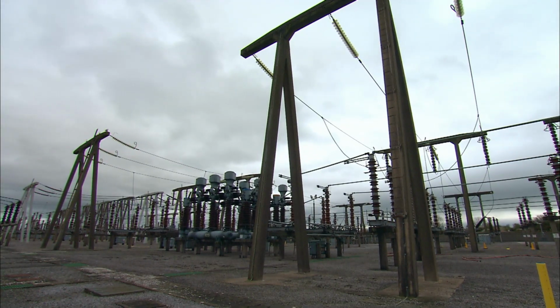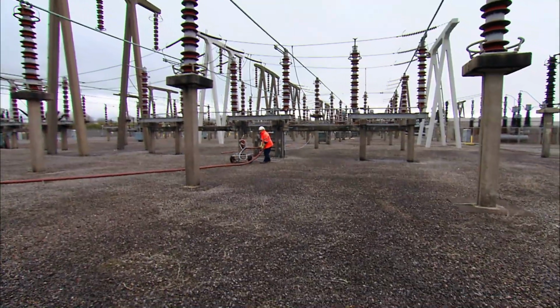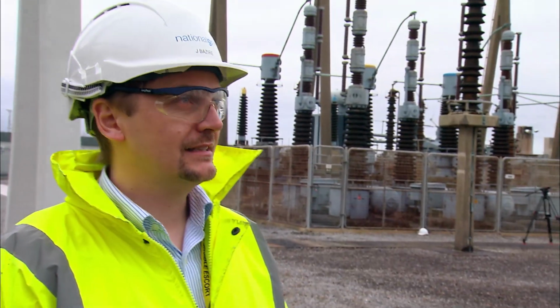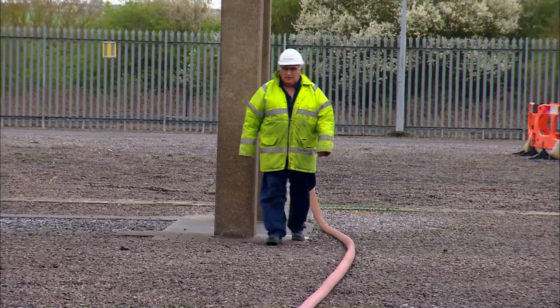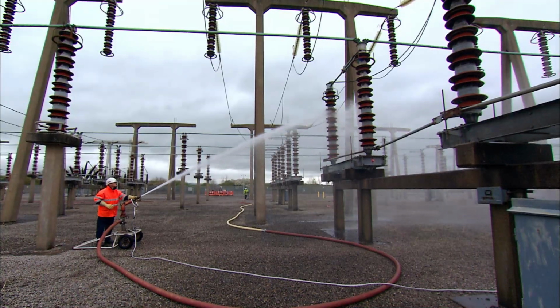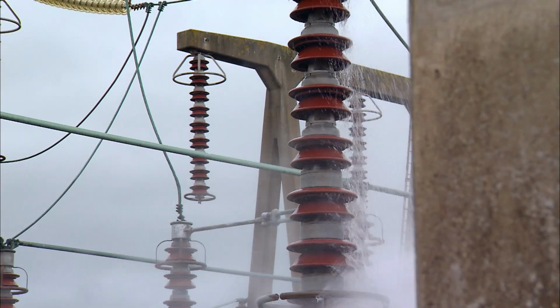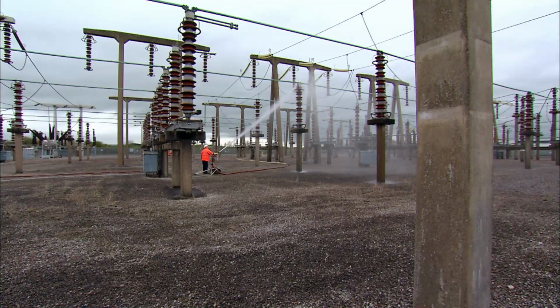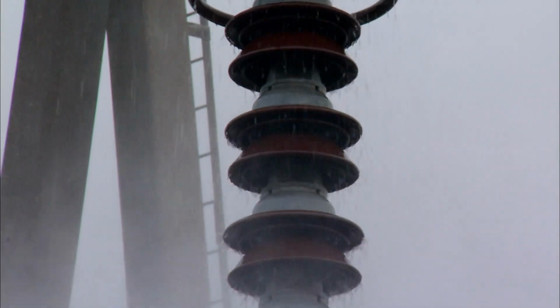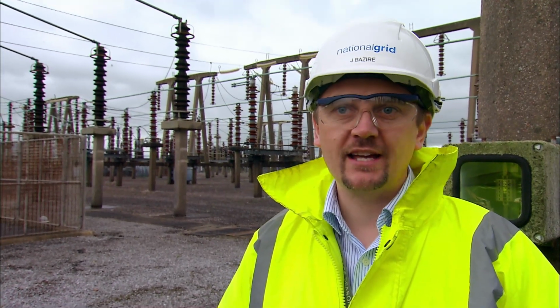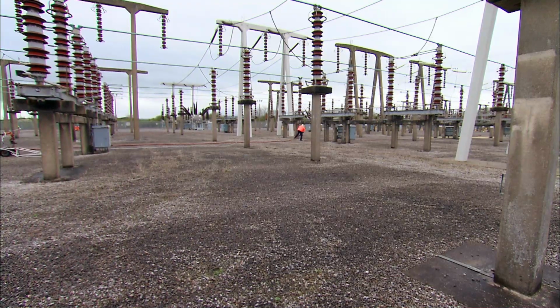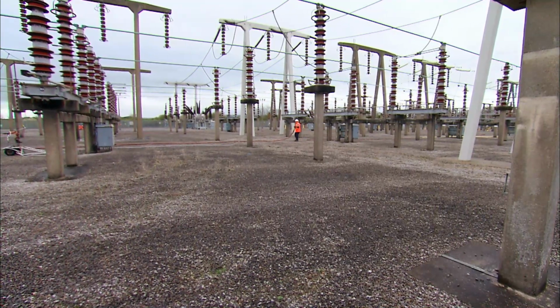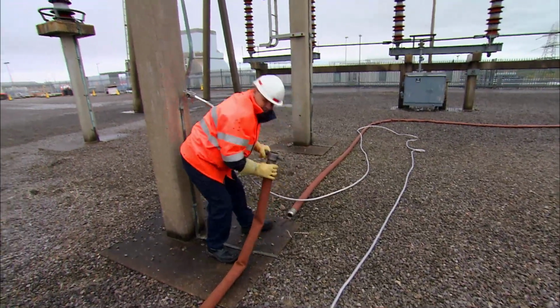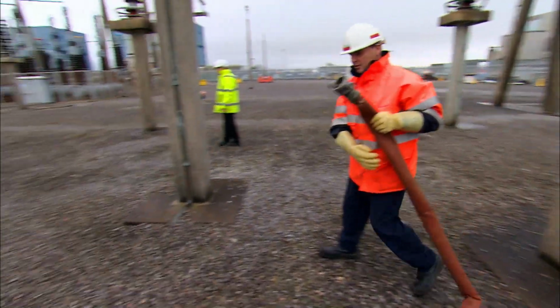At Hinkley Point Electrical Substation, the veteran cleaning team of Pete, James and Frank is well underway with the water wash. They're washing salt from the vital insulators and jetting water directly onto the live 275,000 volt conductor. These guys have done a great job. It's taken 2 days to wash this substation. They've washed 250 stacks. This means that this site will run safely and reliably for the next couple of weeks without any problems.